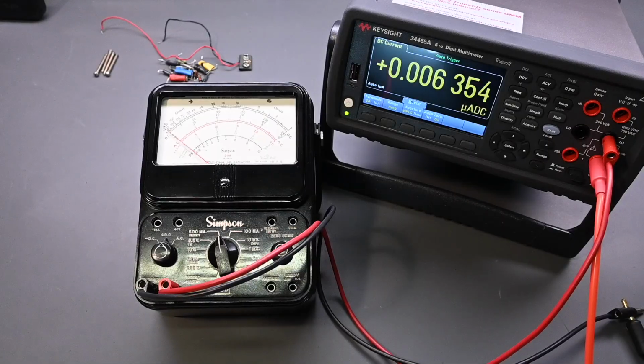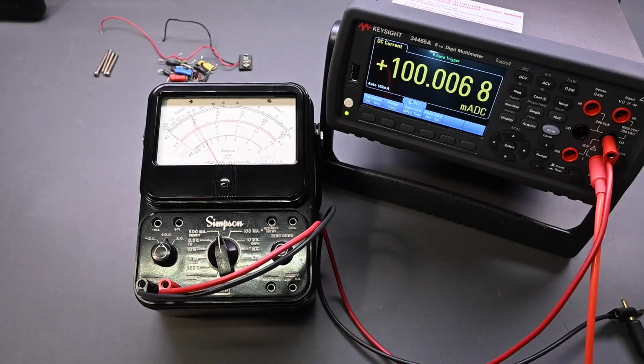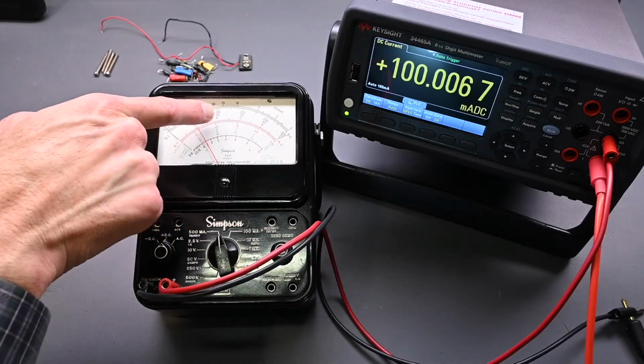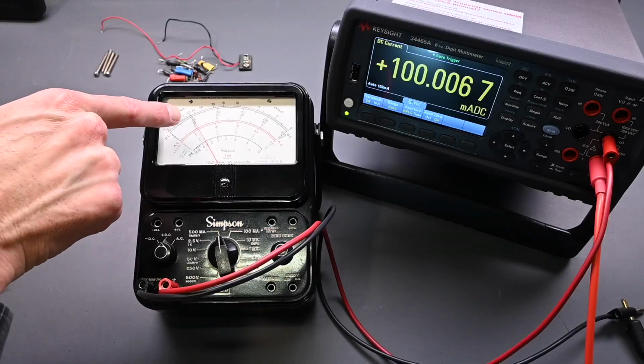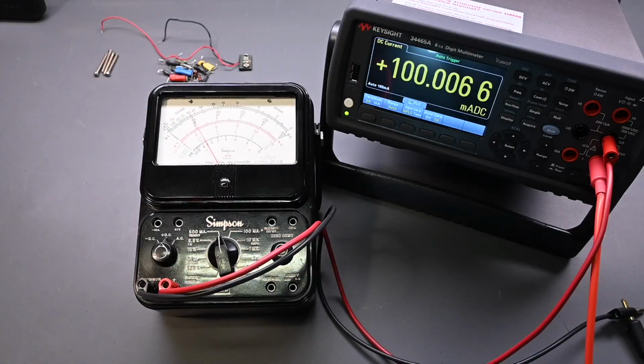Start here with, this can only go up to 100 milliamps. So let's go right here. Let's see, we need to enter, operate. Okay, that is not where we want to be. It needs to be, there it goes. Perfect. Okay, so 100 milliamps. So 100 milliamps there, and looks good. So 500 milliamps full scale, and we're reading this second range numbers down, and perfect. It's right on the tick mark. So no problems there.